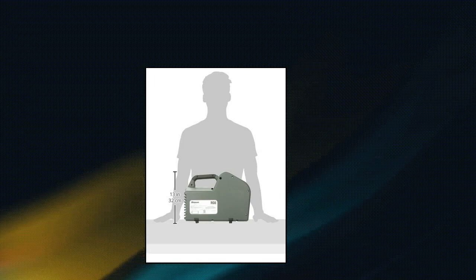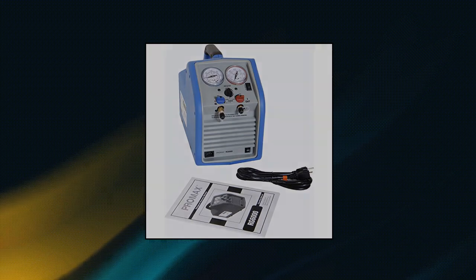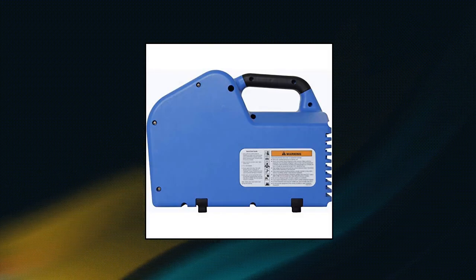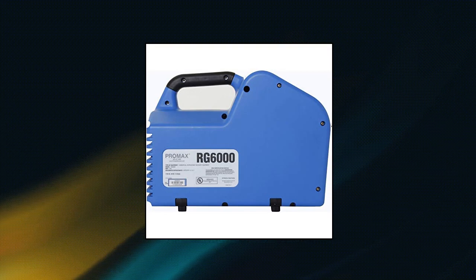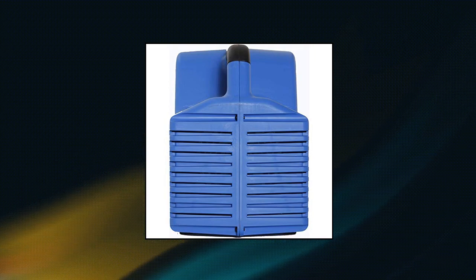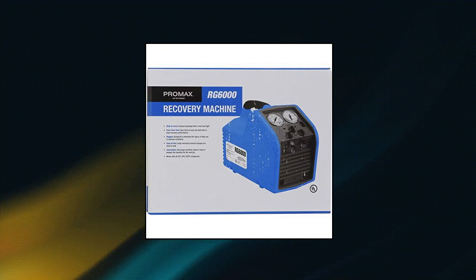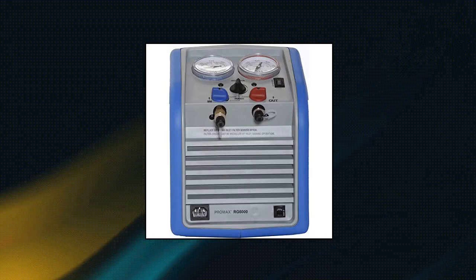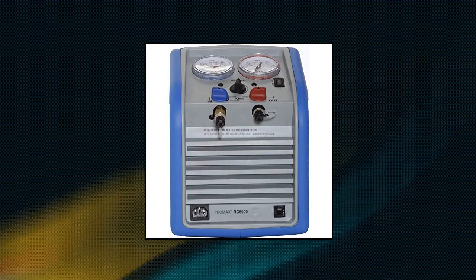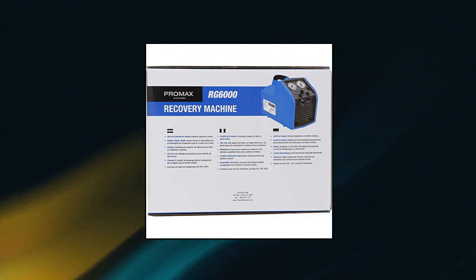ProMax RG6000 Portable Refrigerant Recovery Machine. Easy to operate, twin cylinder design provides best-in-class recovery performance and features a rugged case, oversized pressure gauges, comfortable handle, and simple controls. The RG6000 works with all common CFC, HFC, and HCFC refrigerants including R-410A. Three-quarters of a horsepower, 115 volts AC, 60 hertz twin cylinder oilless compressor is capable of recovering both liquid and vapor. High pressure safety shutoffs automatically shut the machine off if pressure rises above 550 PSI. Self-purge feature eliminates potential for cross-contamination and saves time.